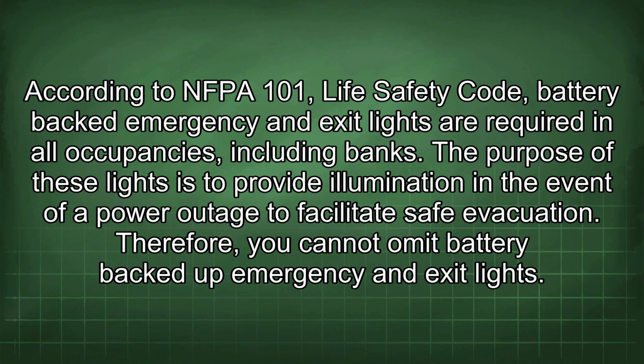According to NFPA 101, Life Safety Code, battery-backed emergency and exit lights are required in all occupancies, including banks. The purpose of these lights is to provide illumination in the event of a power outage to facilitate safe evacuation. Therefore, you cannot omit battery-backed up emergency and exit lights.